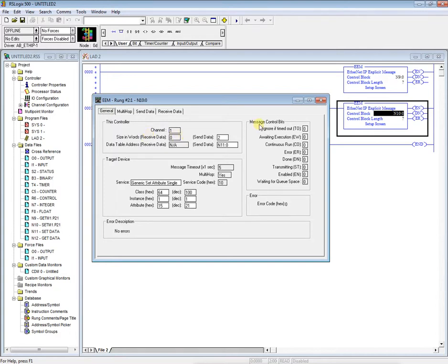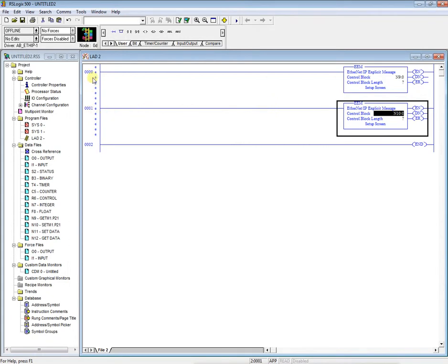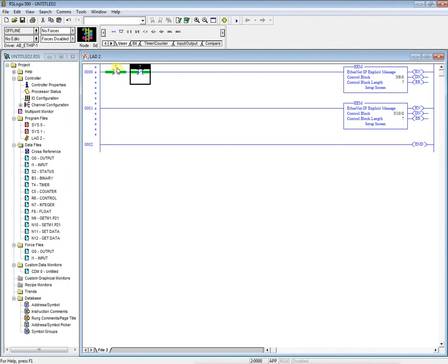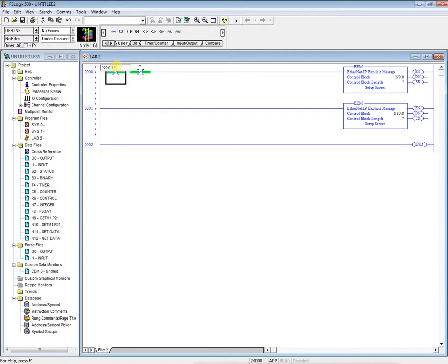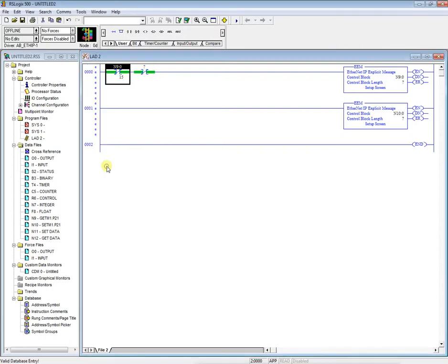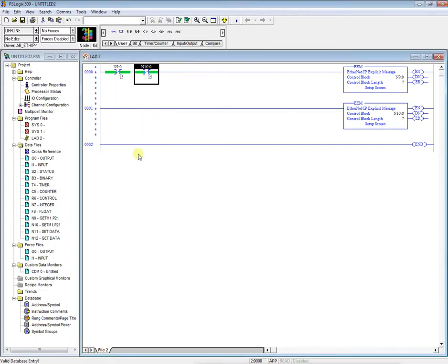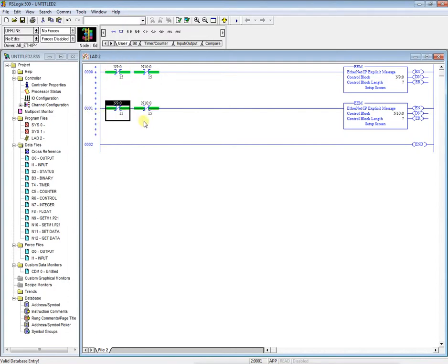So now that we've set up our EEM instructions, we can come over here to the leading rung logic. And we'll put in two normally closed contacts or examine if closed contacts. We're going to do this as N9 colon 0 bit 15. This will be the enable bit for the get instruction. And then we're going to do the enable bit for the set instruction. And we'll copy and paste this down here.